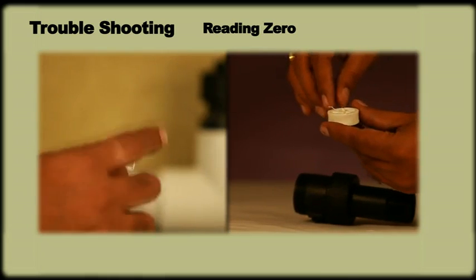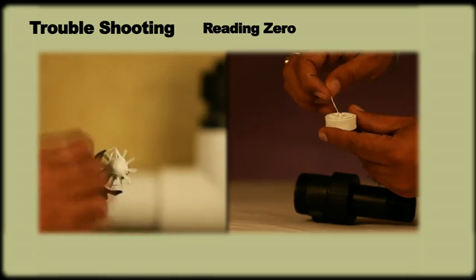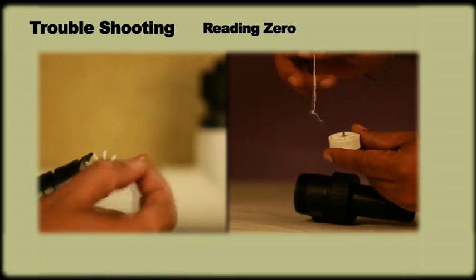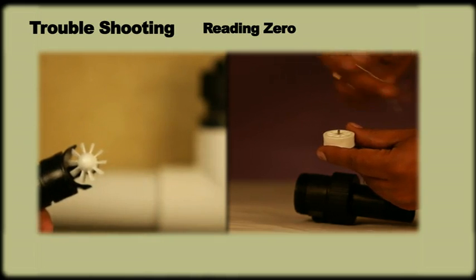If you find that the sensor turbine isn't rotating freely, remove the sensor and clean the turbine ensuring free movement of the turbine wheel.